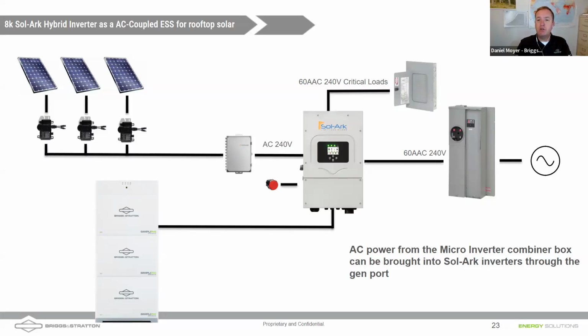What's really cool about these newer hybrid inverters is that with that PCS or CRD listing on their UL 1741, we can put in a larger breaker than 40 amps, and that we trust, because UL tested it, that yes, it can draw 60 amps out of the load center, out of grid, and send it up to our critical load. So we're making sure we can pass through 60 amps right here, but we're never going to backfeed more than 40 amps. And that's a really cool feature, so that we're not limited by that 40 amp breaker like we were with that 120% rule when we didn't have PCS CRD control.